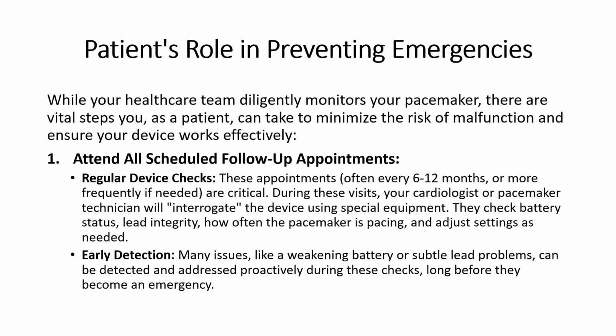During these visits, your cardiologist or pacemaker technician will interrogate the device using special equipment. They check battery status, lead integrity, how often the pacemaker is pacing, and adjust settings as needed. Early detection. Many issues, like a weakening battery or subtle lead problems, can be detected and addressed proactively during these checks, long before they become an emergency.